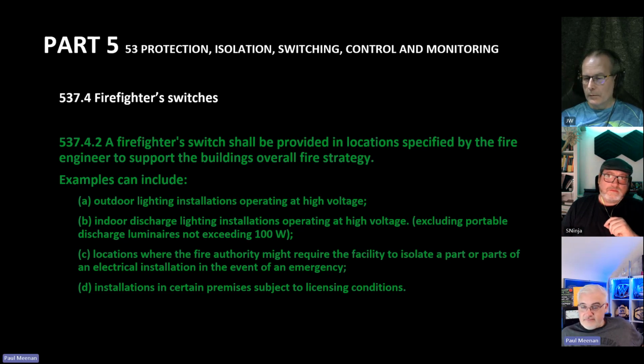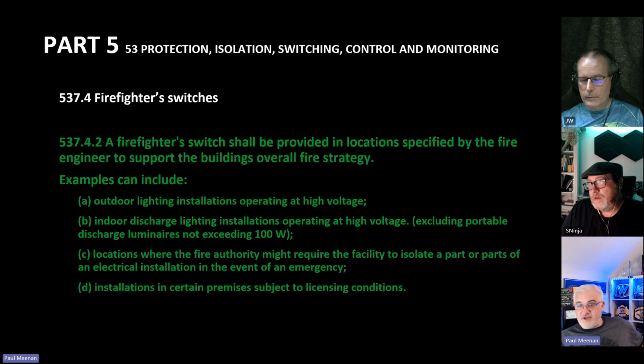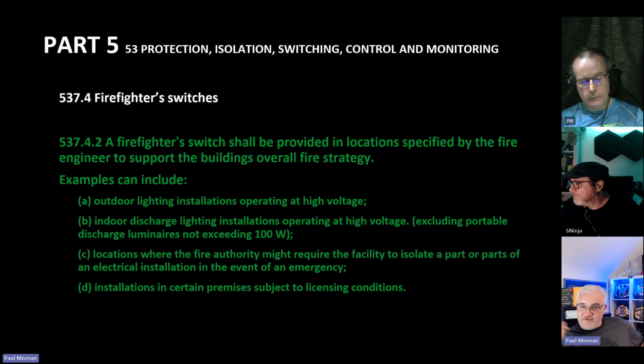I've had a fire recently, and one of the requests from the fire brigade was, we can't isolate the power. Ironically, what caught fire was the main switch, which was the isolator for the power. So afterwards, the suggestion came back of, can you put a firefighter switch, a very simple firefighter switch, that will isolate all sources of supply? Now, in that station, there's two 400 amp supplies and two 200 amp supplies for retail. Now, if I did that, I would need then contactors sufficiently rated for that load, a control system for that, and then effectively a control switch, which would be the firefighter switch, to drop all them supplies out.